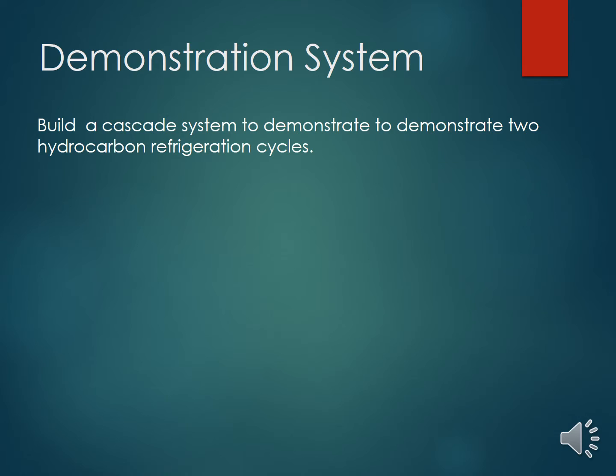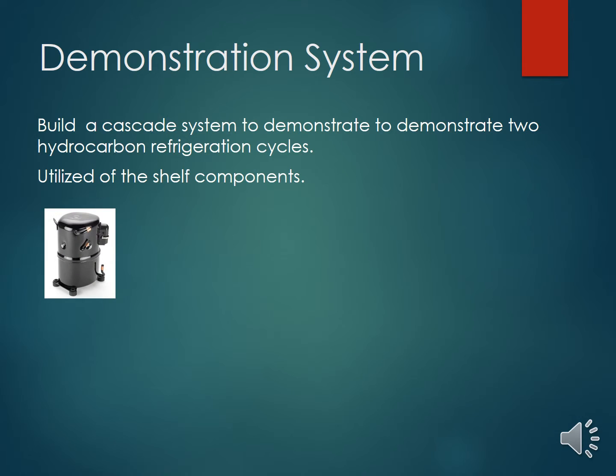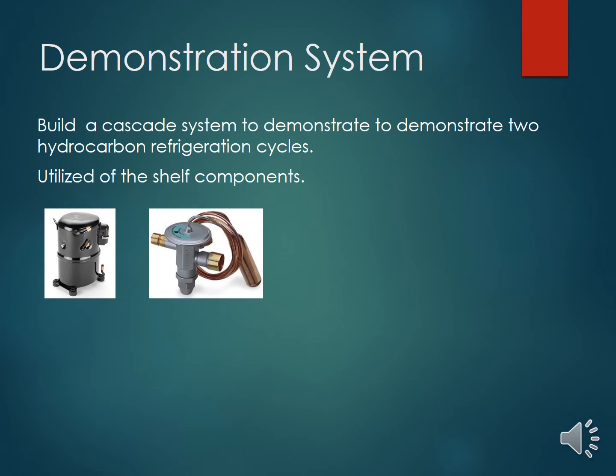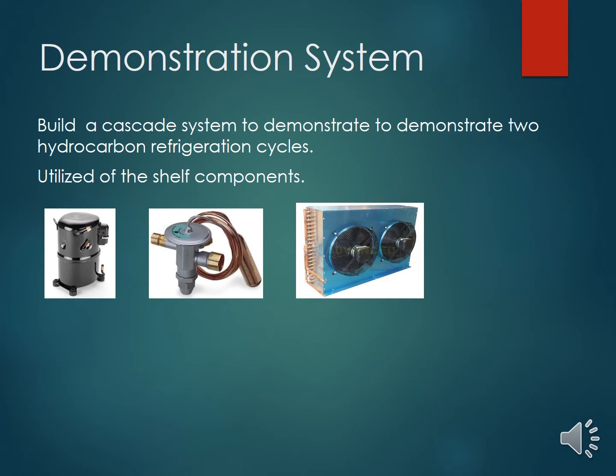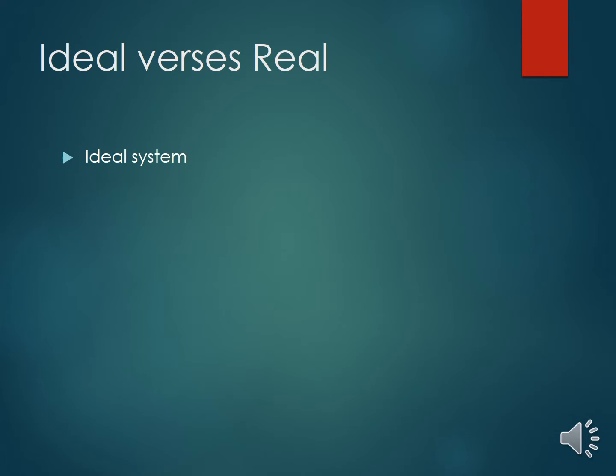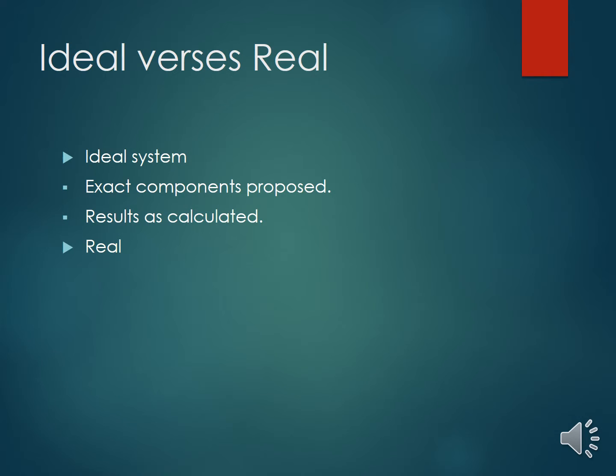The purpose of constructing an operating cascade system was to demonstrate the two hydrocarbon refrigeration cycles. A primary goal during the construction of the system was to utilize off-the-shelf components, such as compressors, thermal expansion valves, and condensing units. The ideal system was a system that was outlined in the paper. It would have used the exact components proposed and calculated for, and would have produced the results as calculated. The real system was a system that was put together as the cost rose above budget, and components were substituted to stay within budget. The system that was put together demonstrated the hydrocarbon refrigeration cycle and showed its viability.